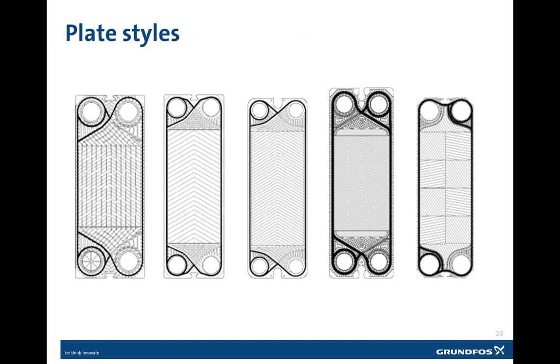So a close approach and low pressure drop doesn't come free. Actually, it's kind of an inverse relationship. The closer the approach and the lower the pressure drop, the more expensive the heat exchanger unit is. So the supplier of this type of device will gladly demonstrate the cost effectiveness of the selection for the system. Also, plate heat exchangers vary in their size, shape, and pattern, which also impacts the selection process. And the plates are also available in a variety of different materials to meet different application needs, including double-walled for potable water type applications.